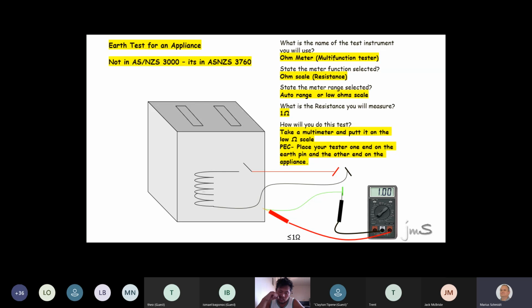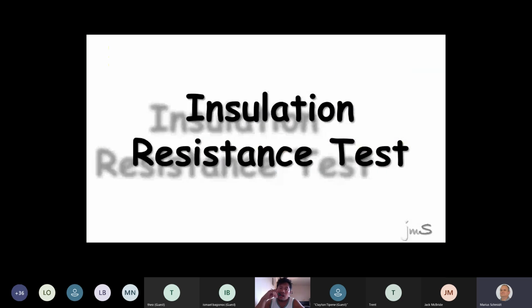1 ohm or less. So recap all the earths before I go to the next test. The others: 1 ohm, half an ohm, or low enough to trip the protection device. Now, a main earth conductor. What's the resistance? 0.5 max. Bonding. Appliance earth. A double insulated earth. An appliance with double insulation hasn't got an earth. Right. What about a bonding conductor? Half ohm or less. Eh?